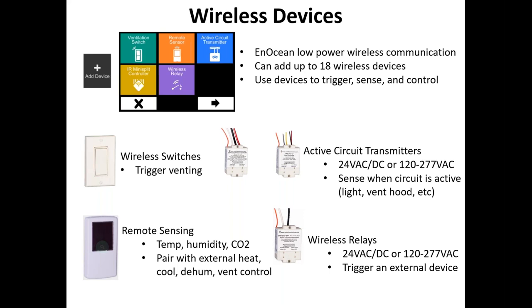Remote sensors: we have temperature, humidity, and CO2 wireless remote sensors. These have different functions that can be used with the CERV. And then wireless relays, like the wired output channels, can be used to trigger things externally, heating or cooling, the GeoBoost pump, things of that nature.